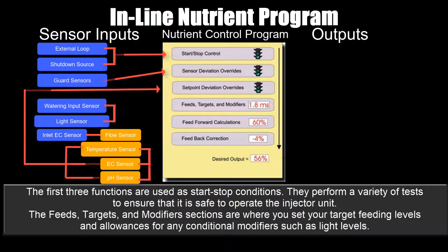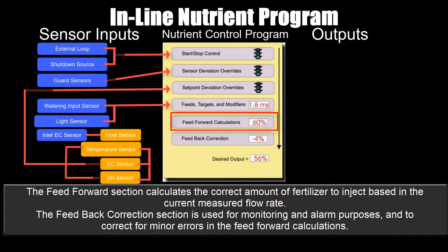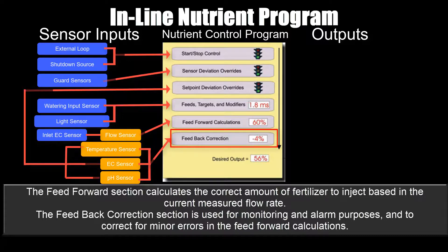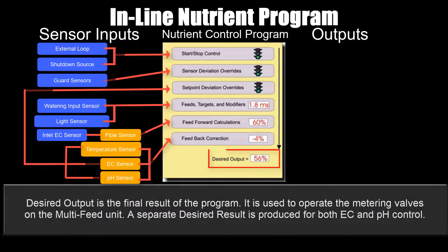The first three functions are used as start-stop conditions. They perform a variety of tests to ensure that it's safe to operate the injector unit. The feeds, targets, and modifier sections are where you set your target feeding levels and allowances for any conditional modifiers such as light levels. The feed forward section calculates the correct amount of fertilizer to inject based on the current measured flow rate. The feedback correction section is used for monitoring, alarm purposes, and correcting minor errors in the feed forward calculations. Desired output is the final result of the program, used to operate the metering valves on the multi-feed unit. A separate desired result is produced for both EC and pH control.